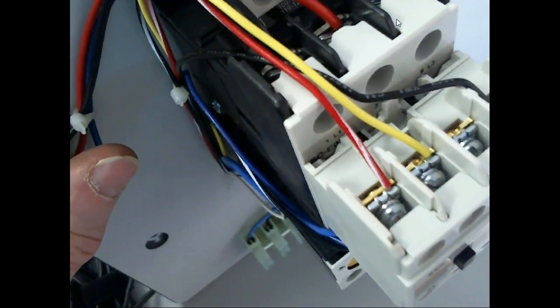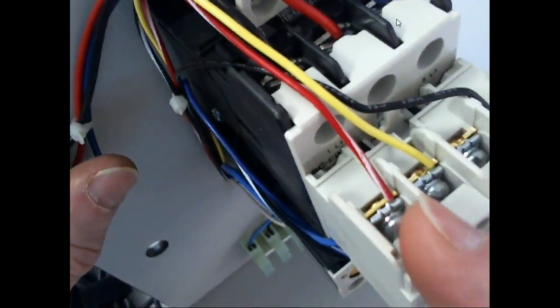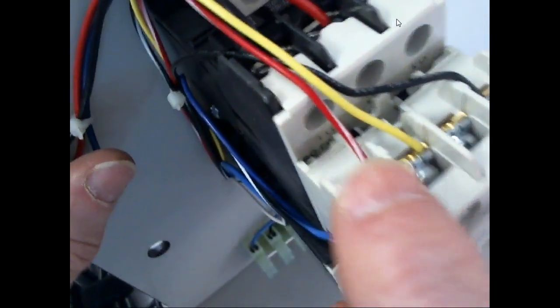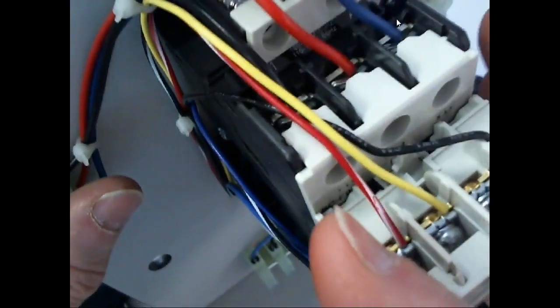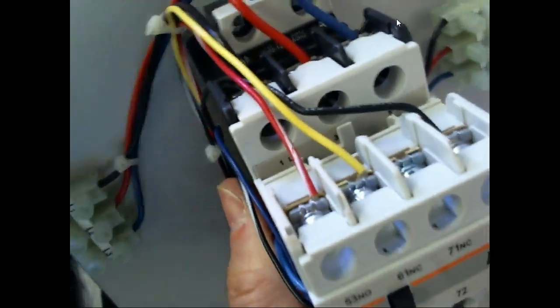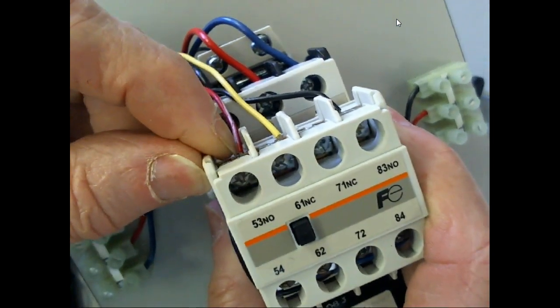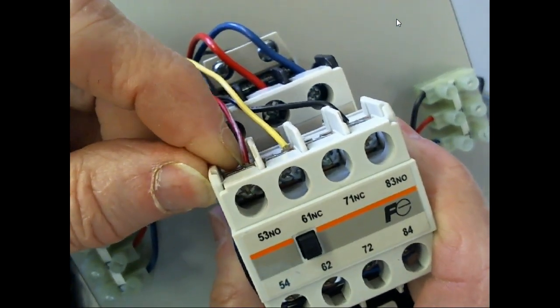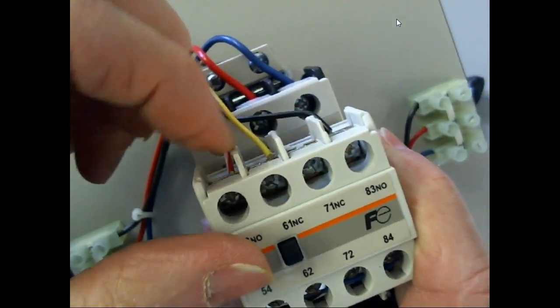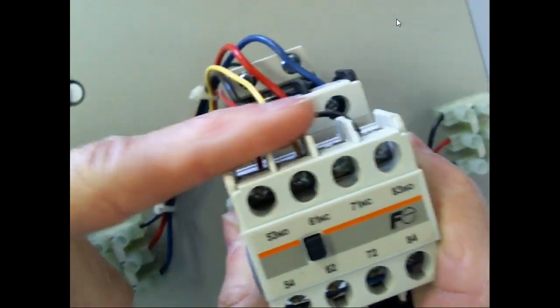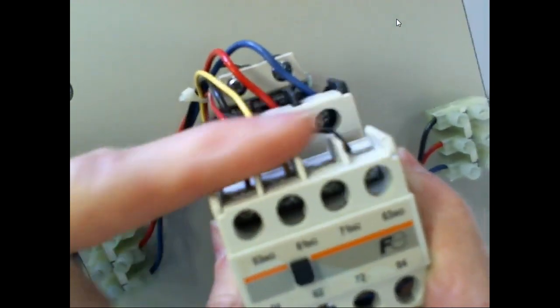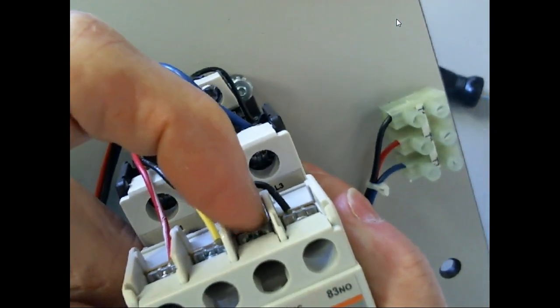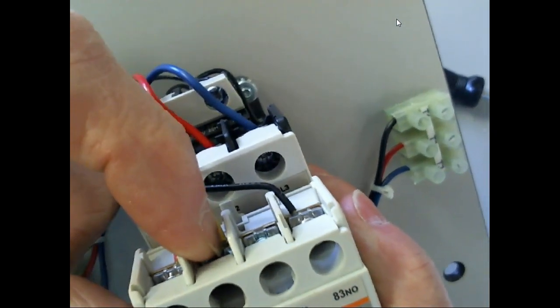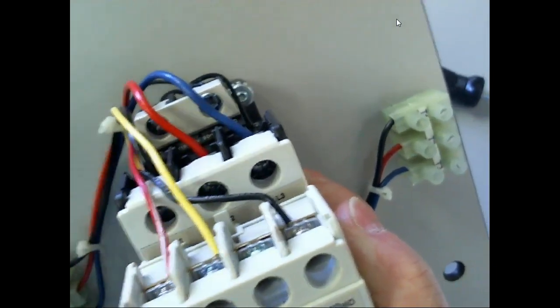The strands can't go anywhere. They're going to always be up under this metal plate right here. So when you unscrew it, the little plate comes up. You stick the wire in there, then you tighten it back down. The rule is no more than one wire diameter coming out between the edge of the insulation and the actual terminal itself. So you don't want a bunch of wires, but you can actually see they even have the troughs out past this, right? You know? So that means if something arcs over here, when it creates ozone, it's not going to be able to get in over here.